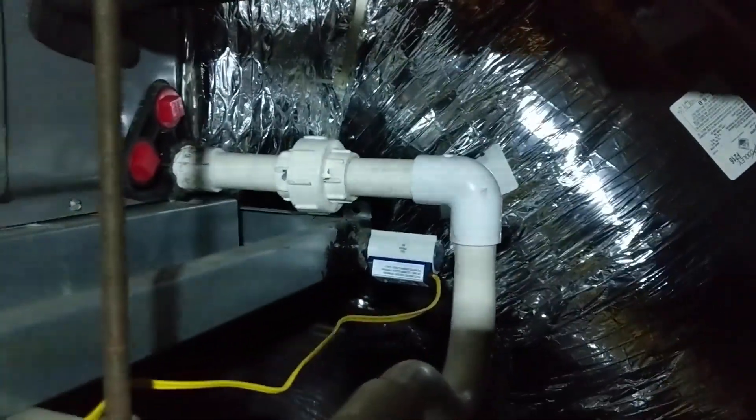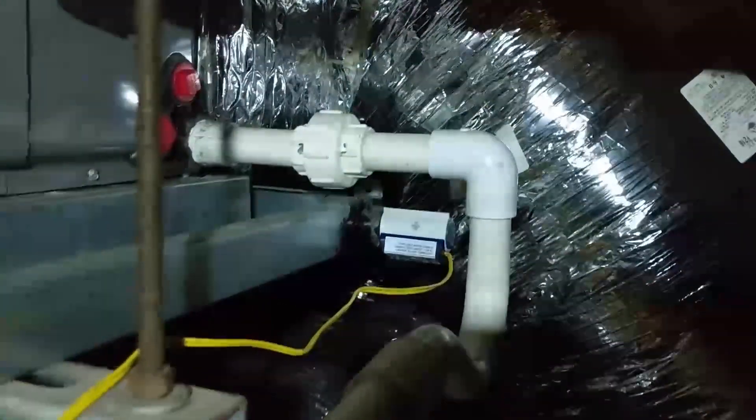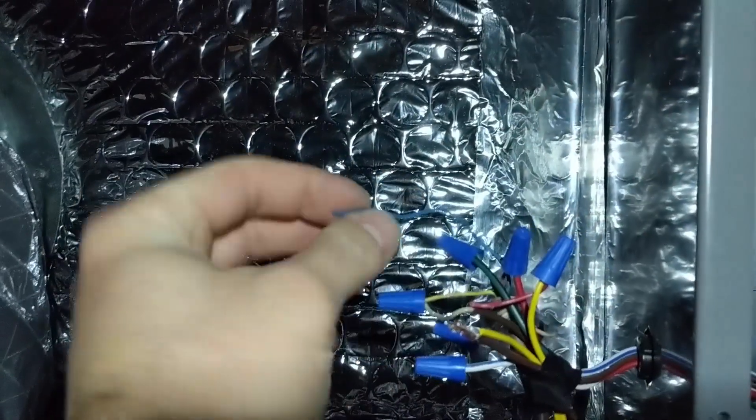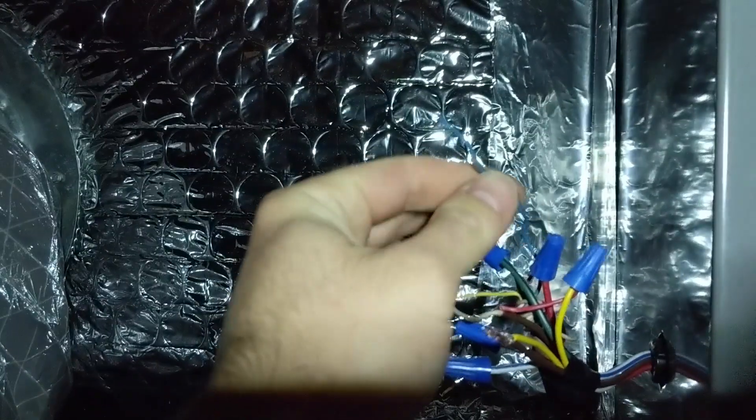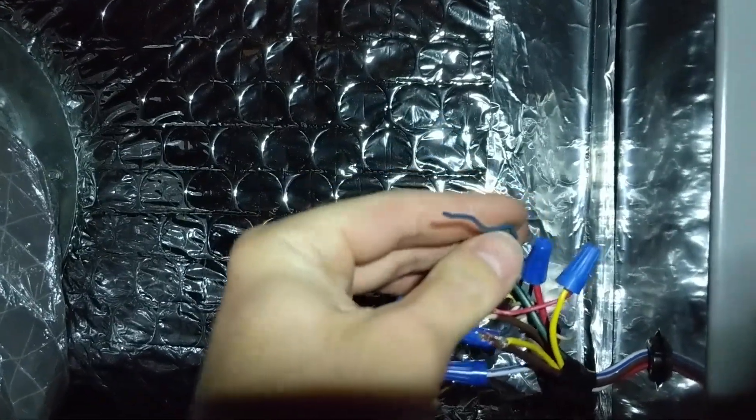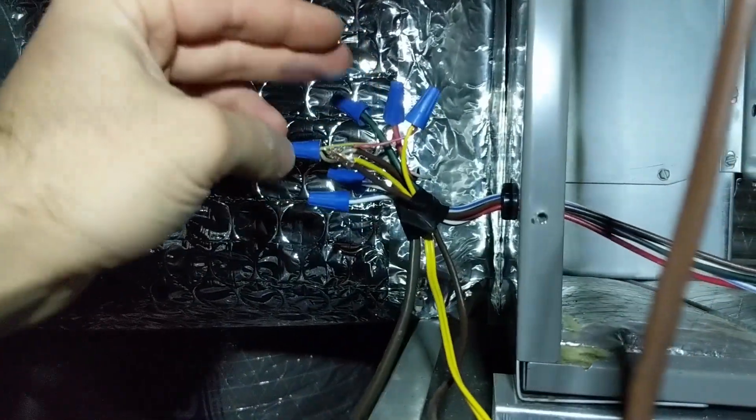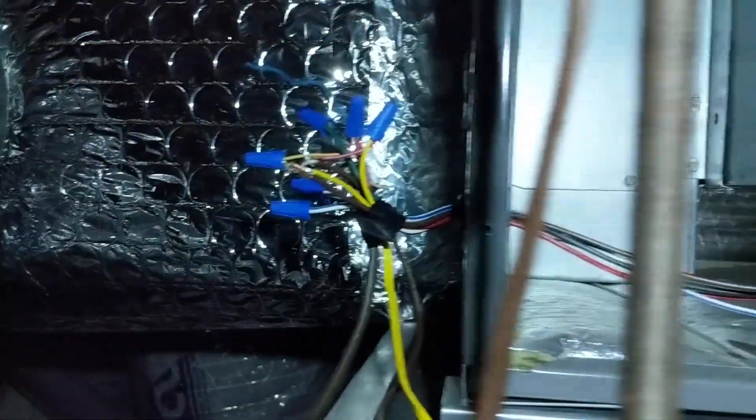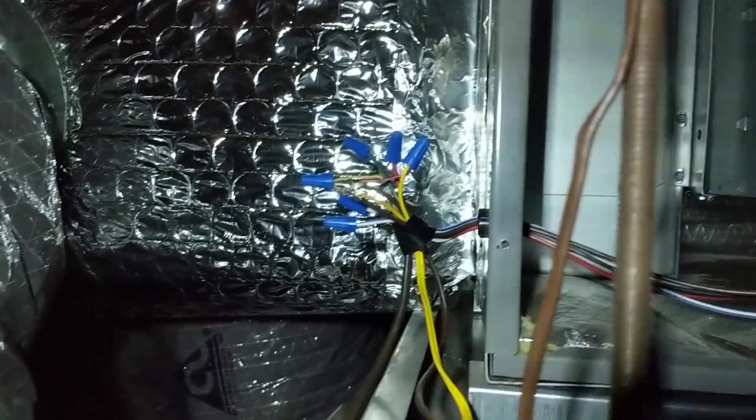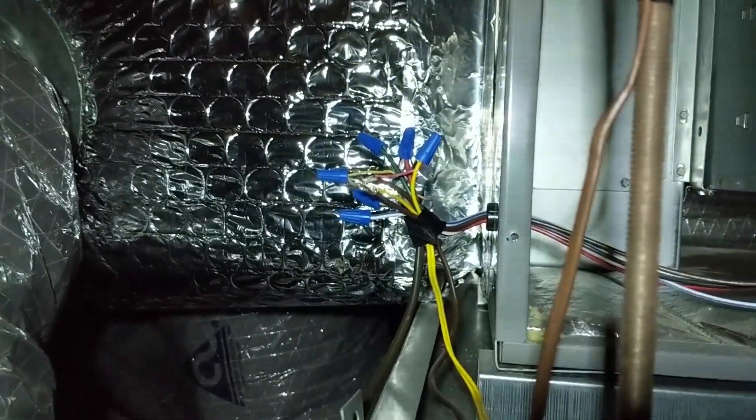I just pulled the wire nut off. I'm gonna strip this blue wire which we stripped down at the thermostat to make the common wire because it was unused. We're gonna twist it in with that, put the wire nut back on, and we will have a common wire and that thermostat should work and power both the AC and heat as it was previously.